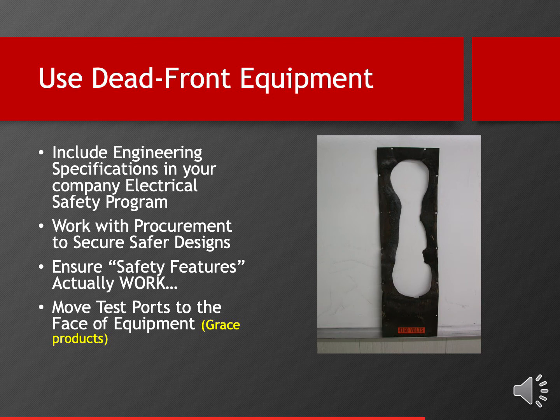Ensure that the safety features actually work on the system. There have been situations where we've had events where they've had dead front doors where the equipment malfunctioned the way it was produced, and you actually had to open the door to access to do the racking out of a breaker inside the enclosure. It actually had a safety feature that didn't function. And then, of course, another option would be moving test ports to the face of the equipment.